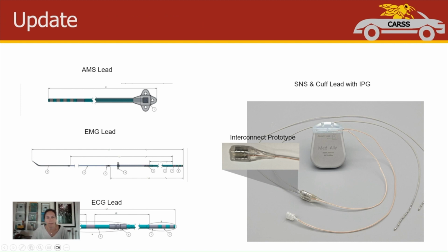Along with Nest 1, we are also developing the partnering leads as part of Nest 3. Nest 3 incorporates a series of standard leads to enable new research. An SNS, or sacral nerve stimulation lead, with 4 contacts, a cuff lead with bipolar electrodes, an EMG sensing lead, an ECG sensing lead, and an accelerometer-based motion sensing lead. The lengths of these leads can be customized per application. Additionally, there is an interconnect that will allow a 4-contact lead from the header to split into 2 bipolar leads that will allow for further customization and integration with various sensor modular leads being developed in the additional nests.